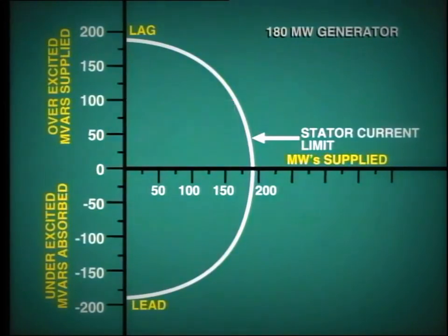Clearly, in order to keep within the MVA rating, we must reduce megawatt output if we wish to produce a large output of VARs with the generator.